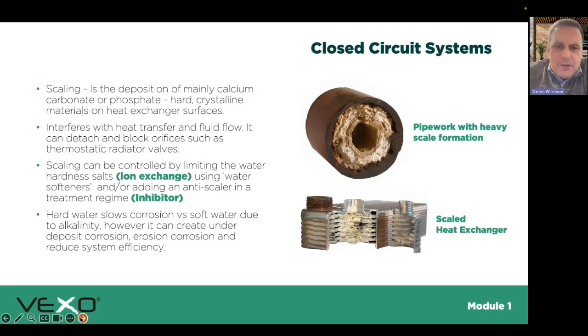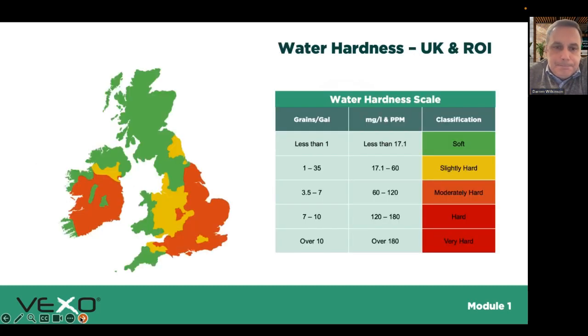We can control this through ion exchange, i.e. water softeners, or by adding an inhibitor, which prevents scale from precipitating out of solution under temperature. Depending on where the project is - UK or Republic of Ireland - you should consider whether pre-treatment is needed for the system, whether there are leaks, or whether inhibitor is being added at all. It's just something to be aware of.